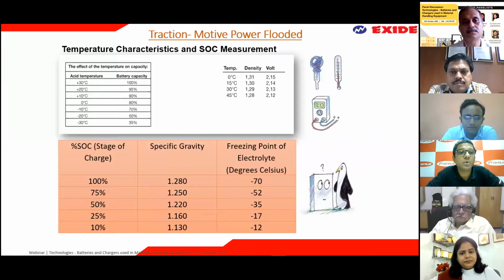Continuing on batteries used in cold warehouses - typically there's an anti-room where a temperature of 0 to 10 degrees is maintained, which is normal for charging. But in places like Europe, this has happened many times where they charge the battery in minus temperatures too. So a specific protocol is required: when charging the batteries, you need to first warm the batteries, bringing them to that particular temperature level. Afterward, the battery can take the charge. Otherwise, the battery cannot take the charge, and you won't get the backup needed for operations.